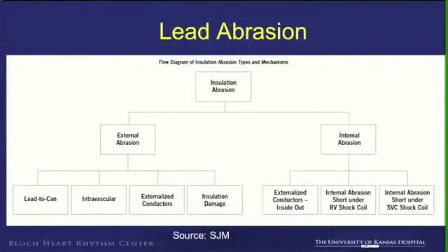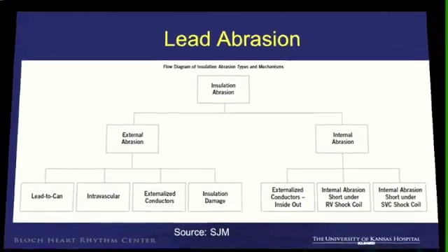Again, lead abrasion, I just want to touch base on that because this is one of the things which we're going to talk about. It's classified into different categories. You have external abrasion or internal abrasion, and external abrasion can be because of many reasons, and internal abrasion can be because of many reasons. So the mechanism of any particular abrasion is completely different from the other. So we need to get into the details as to what exactly is happening. Is it inside out or outside in? Determining the mechanism of the failure will help us project what can happen to the current leads.